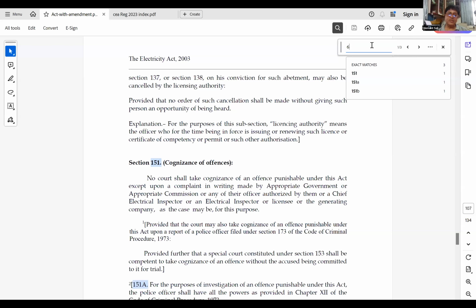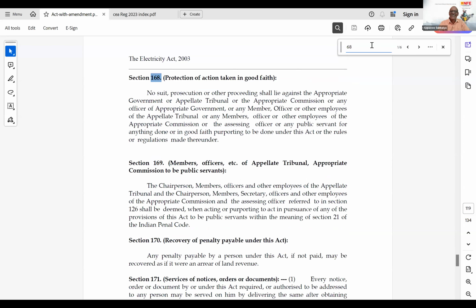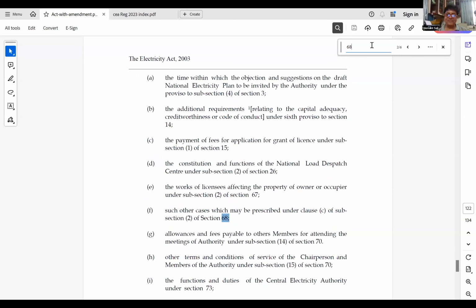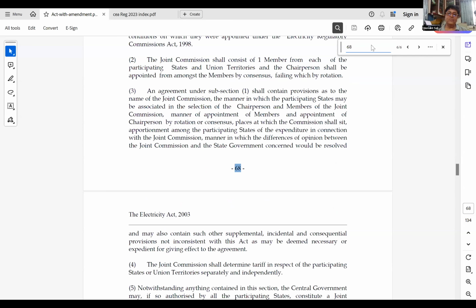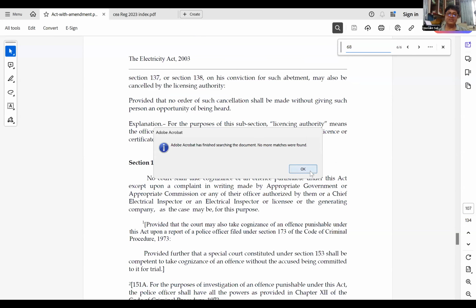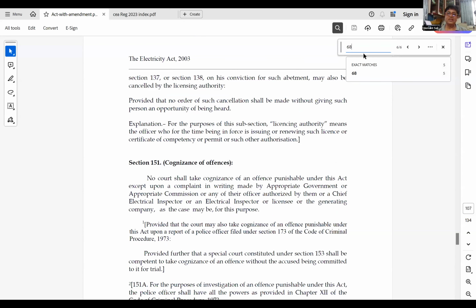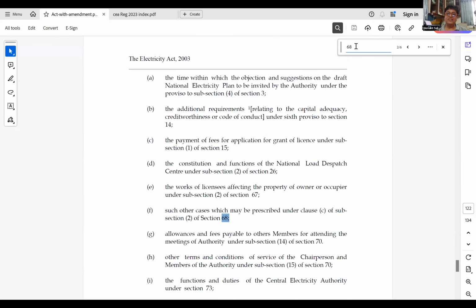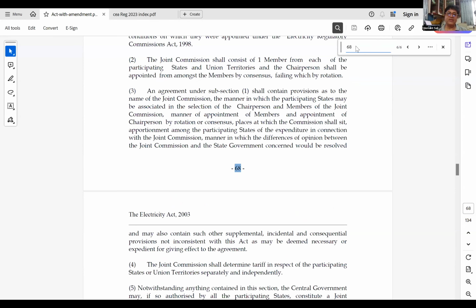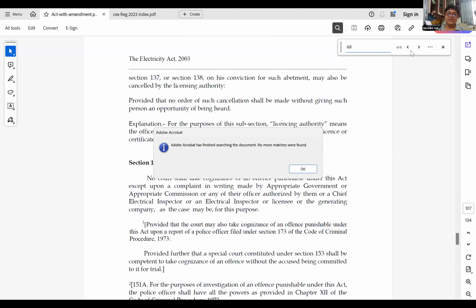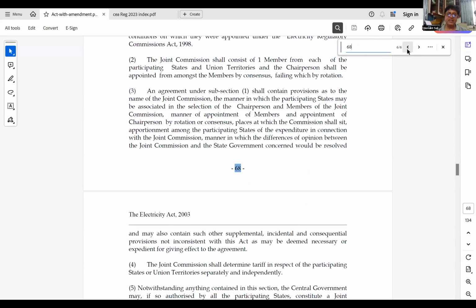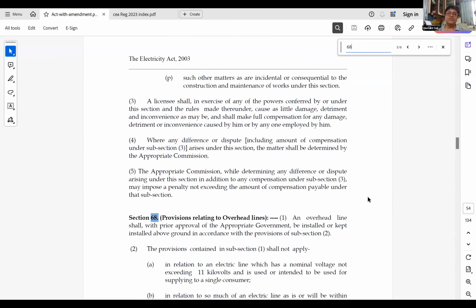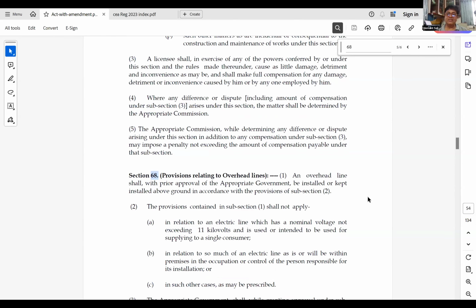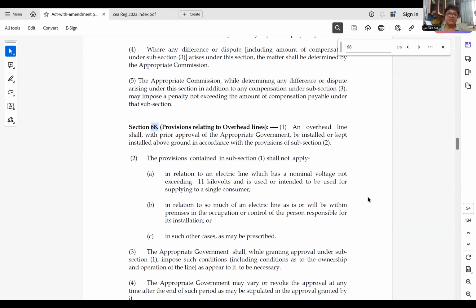One more section, sir, you just mentioned, that is section 68. Sir, if you see Form number 20, which is mandatory for every state to report to the Central Electricity Authority the number of accidents happening, one of the reasons mentioned is accidents due to the snapping of conductors. And if you see the reports submitted under Form number 19 and 20, maximum accidents happen because of conductor snapping in overhead lines. Even in underground cables, accidents are occurring.